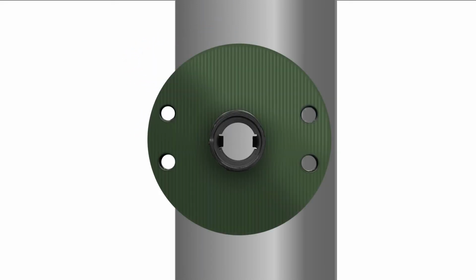Check the depth of the bore with the barrel of the probe. If the barrel is too long, this can be sawn off to size. If the tank has a steel or plastic outer jacket, clean the surface where the probe will attach with an alcohol wipe. Secure the probe mounting flange by removing the backing paper from the sticky pad. Then bend and press the flange flat against the curved surface. If needed, use the 4 self-tapping screws supplied to provide the flange with additional fixing strength.